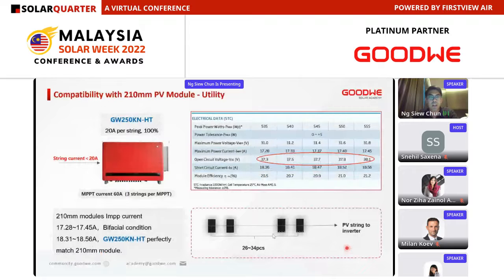So for example, looking at the 210 with the string current of 20 amps, we can actually put 26 to 34 pieces of panels in one string. That is the reason why we do not need so many strings or so many numbers of MPPTs. And of course, this is also due to the characteristic of the panel itself, that the VOC is particularly lower than others, which allows more panels in one string.